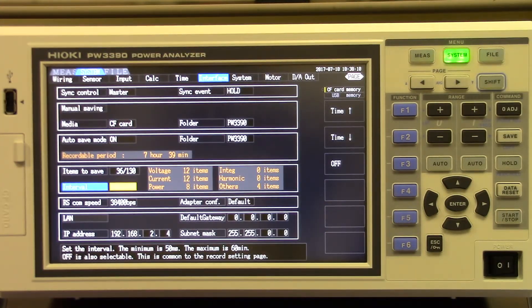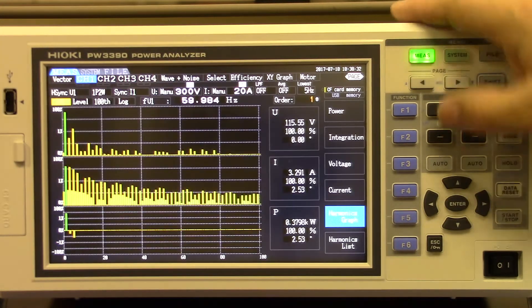The PW3390 allows the user to customize the data they want to log using a recording interval which can be as fast as 50 milliseconds. Recordable data that is available is voltage, current, effective power, apparent power, reactive power, power factor, phase angle, efficiency, integrated current and power, and harmonics up to the hundredth order.